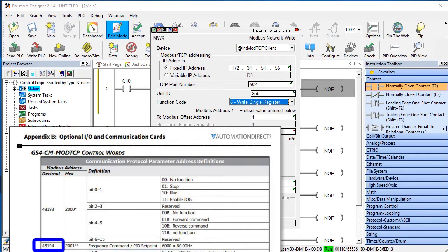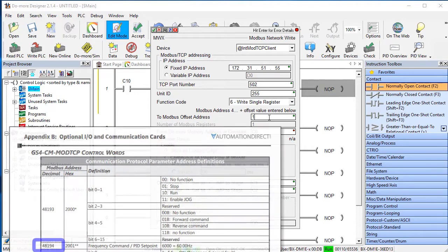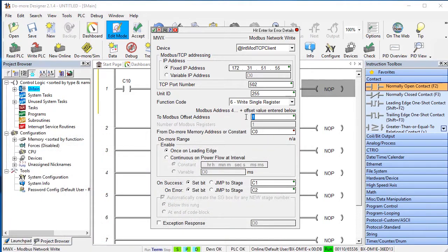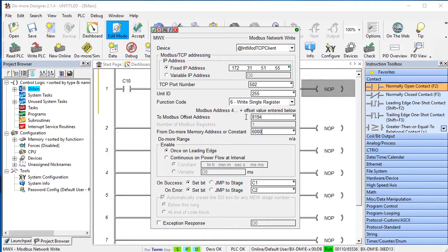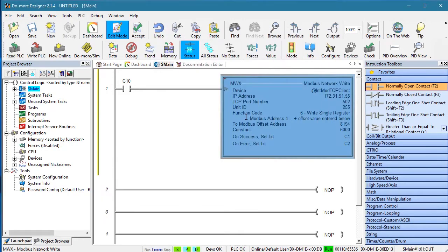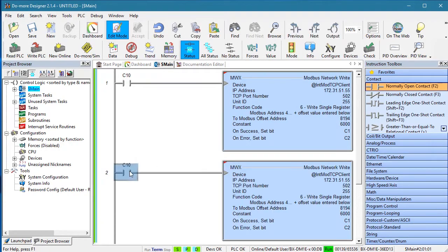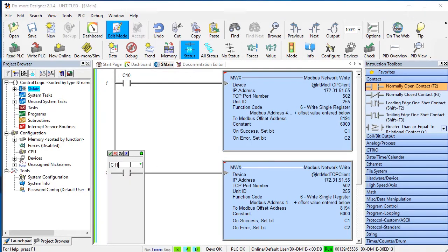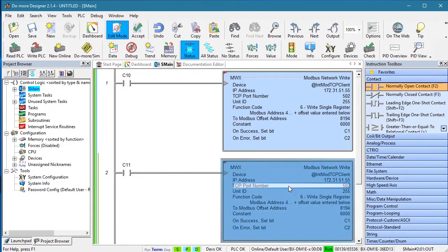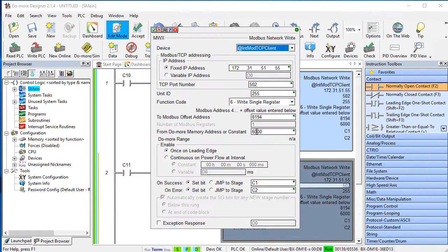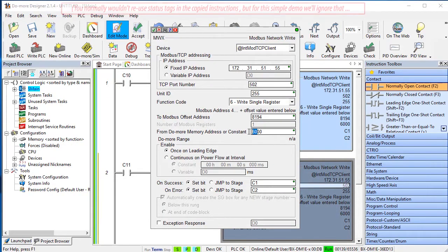And since this chart uses the plus 1 addressing convention for decimal addresses and that's exactly what the DoMore PLC expects, we put that here. The DoMore prepends the 4 for us. And let's set the frequency to 60 Hz. Let's copy and paste that rung and modify it so C11 changes the frequency to 45 Hz.